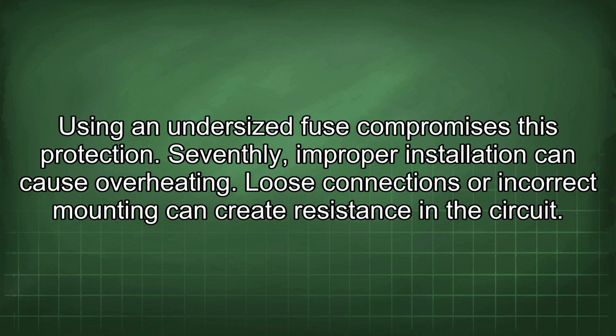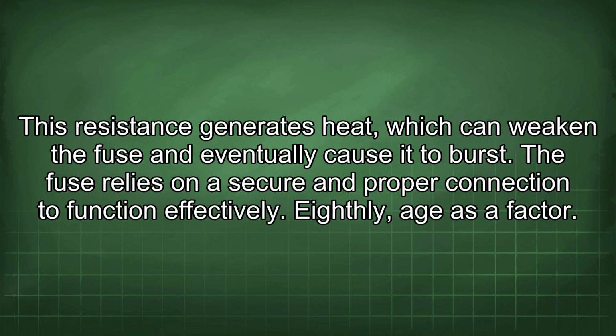Seventhly, improper installation can cause overheating. Loose connections or incorrect mounting can create resistance in the circuit. This resistance generates heat, which can weaken the fuse and eventually cause it to burst. The fuse relies on a secure and proper connection to function effectively.